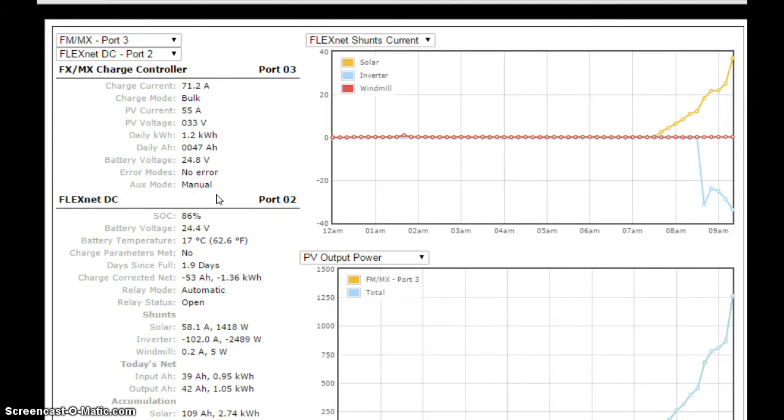Now, one other thing you want to be careful of gets even more confusing: there's a function on an inverter called HBX, which is high battery transfer. It means when the battery reaches a certain voltage, say 27 volts, it will drop the grid and start using the inverter. It will use the inverter until the voltage reaches your low point, which is like 24, 23 volts. At that time, when the battery is getting low at 23 volts, it goes back onto grid and lets your batteries charge back up to 27. Then it drops grid again and goes back to 24. So it keeps the inverter system running. Now, there's a lot involved in that, with delay times and whatnot, to make sure your battery stays up to charge, because you don't want to lose too much, as I was saying.